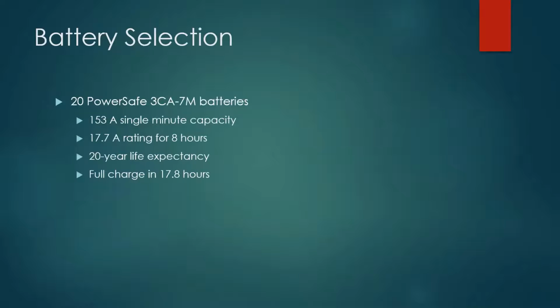Now, to select a battery meeting all of the criteria we've talked about, we decided on 20 PowerSafe 3CA-7M batteries. This bank would give us 153 amps of single-minute capacity, greater than the 144 amps from our duty cycle. It's also rated for 17.7 amps of power for 8 straight hours, which is also greater than what we showed in our duty cycle. They have a 20-year life expectancy and are able to reach a full charge in 17.8 hours.